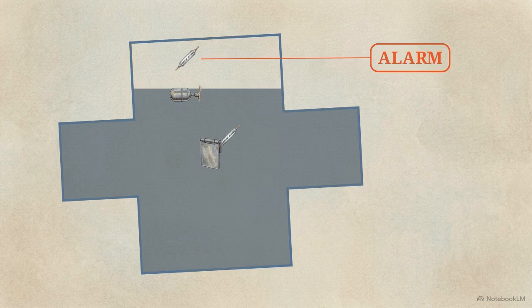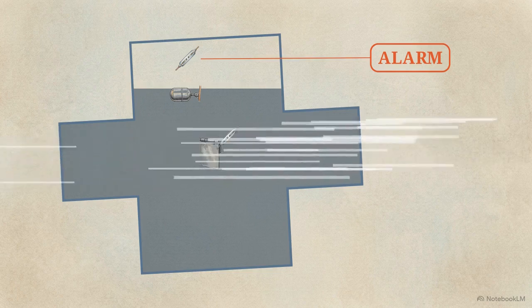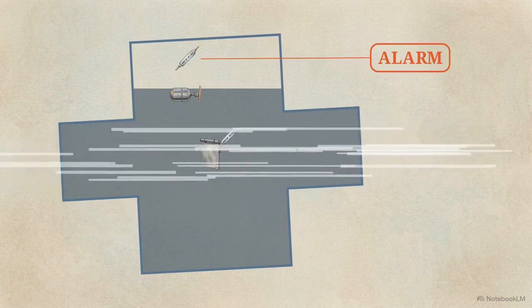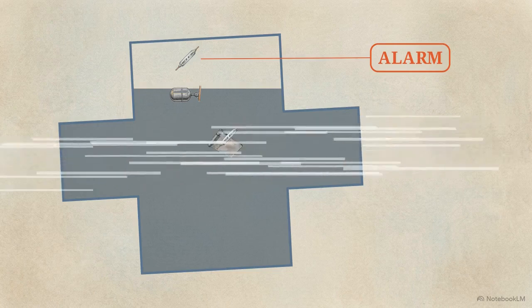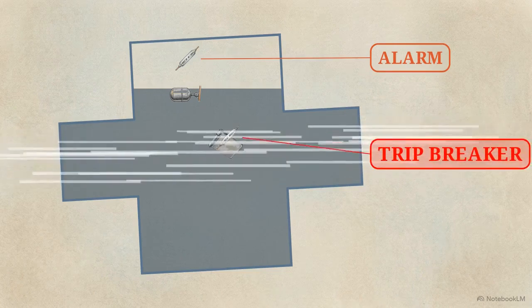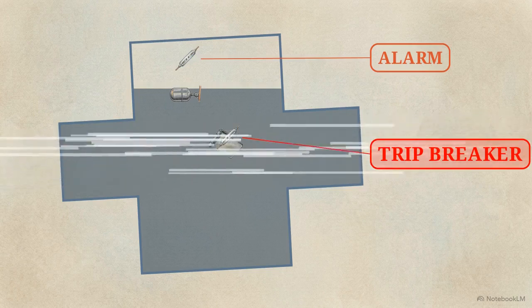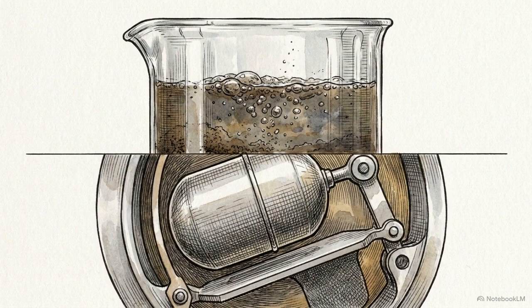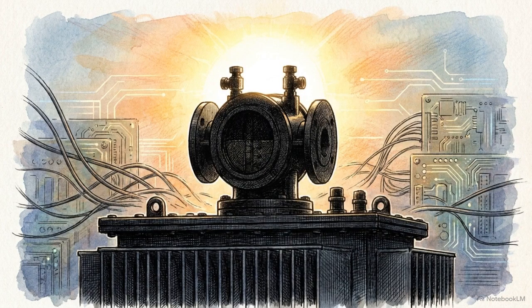In the event of a severe internal short circuit, gas generation is explosive. It forces a massive, violent oil surge through the pipe toward the conservator, typically reaching speeds over 100 centimeters per second. This oil surge slams directly into a lower baffle flap. The kinetic force pushes the flap backward, instantly closing the second magnetic switch. This bypasses all electrical time delays, directly tripping the breaker to save the transformer. By translating the chemical breakdown of insulation into kinetic, mechanical triggers, the Buchholz relay provides a tier of fail-safe security that purely electrical sensors cannot achieve.